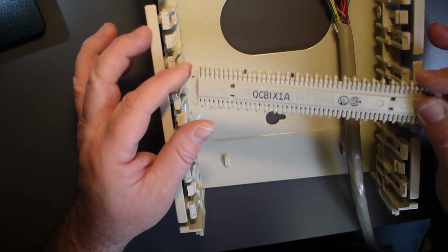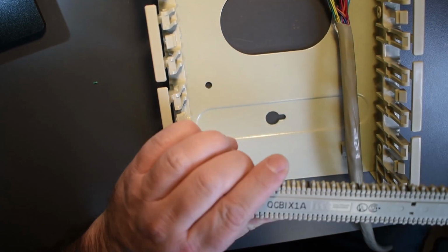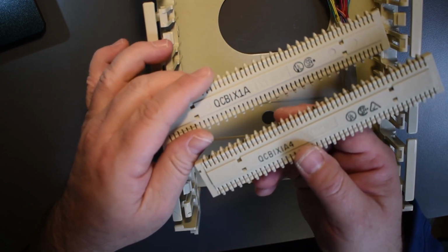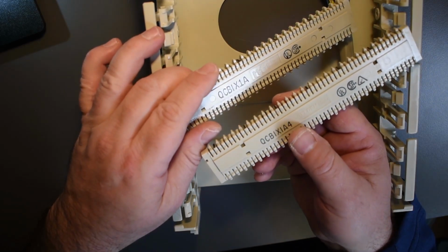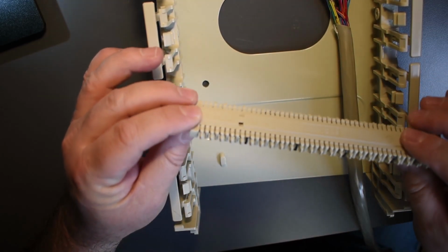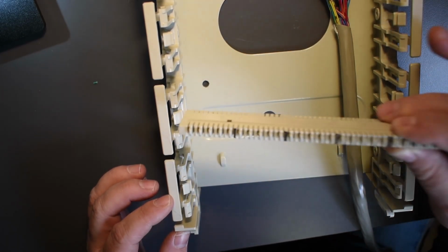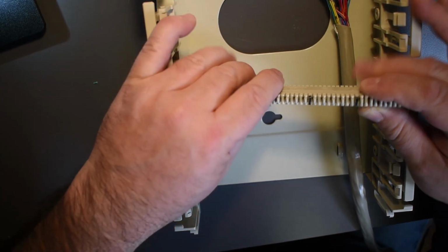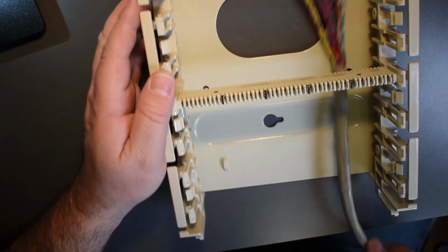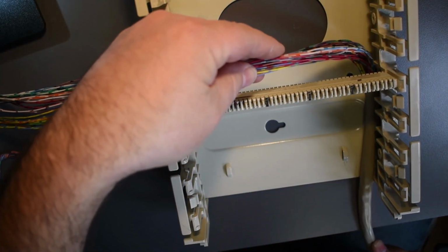Okay. Now I have chosen 1A without any designation numbers after A, but if you just happen to have that 1A4, it will not make any difference. Okay, you're just going to have the designation marks or the orientation marks in a different way. So let's put that thing 1, 2, 3, 4th position here. Going to clip that on, and we're going to bring the wire from underneath, and that's how we're going to terminate this here.